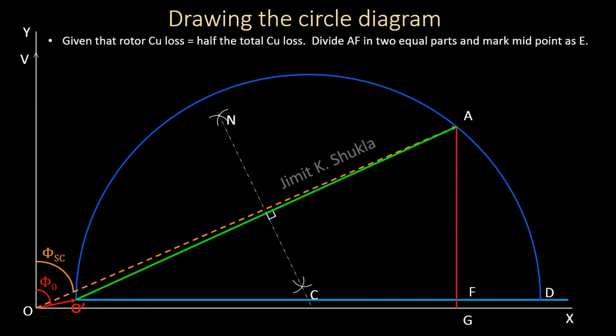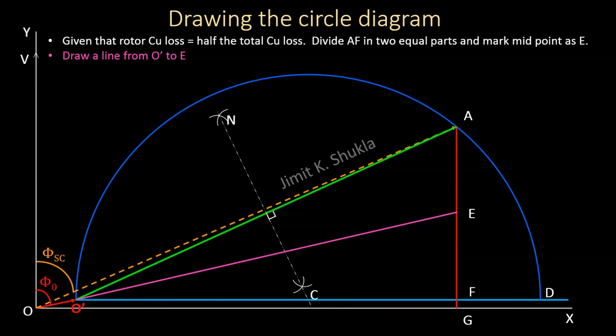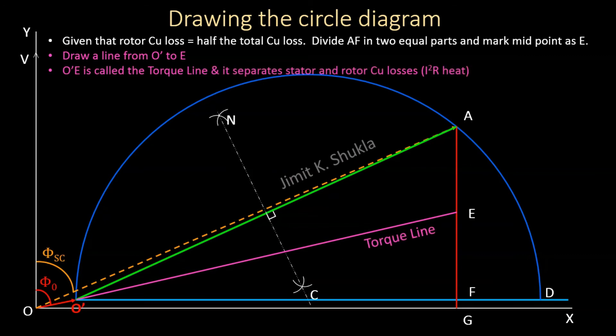Since rotor copper loss equals half the total copper loss, we divide AF into two equal parts and mark the midpoint as E. A line drawn from O' to E is called the torque line, which separates stator copper losses and rotor copper losses. The line O'A is called the output line.